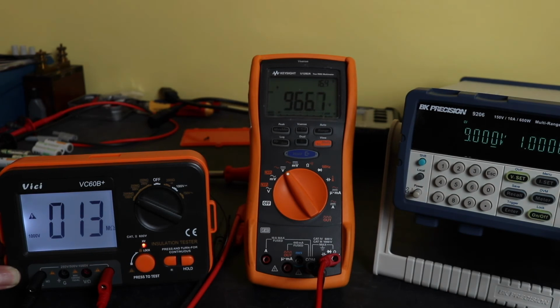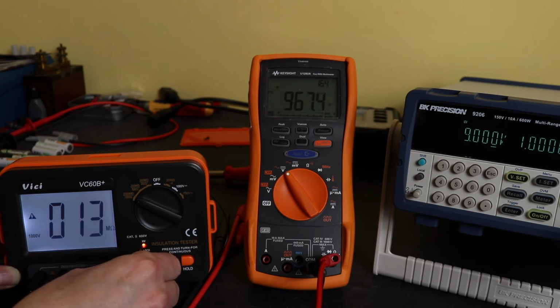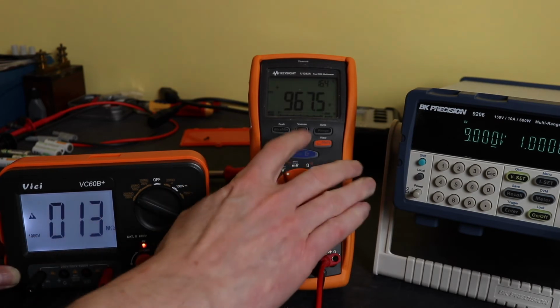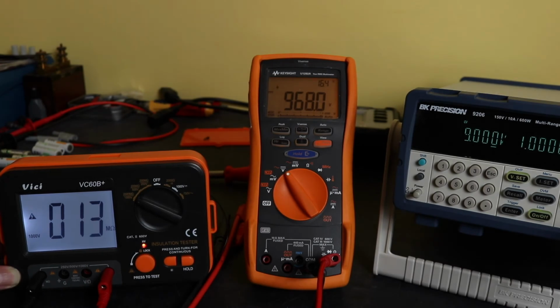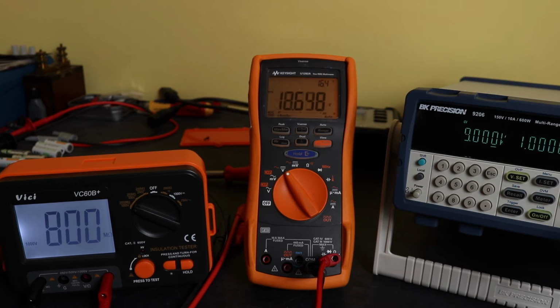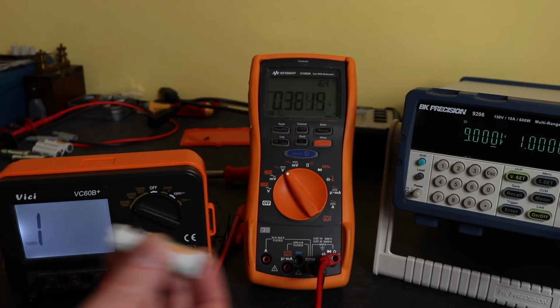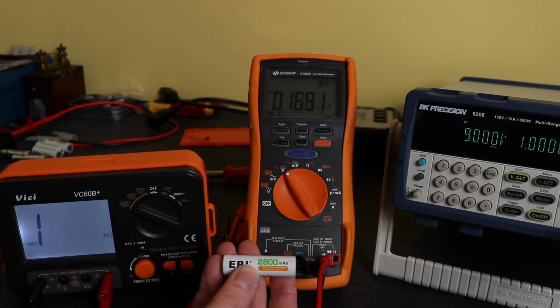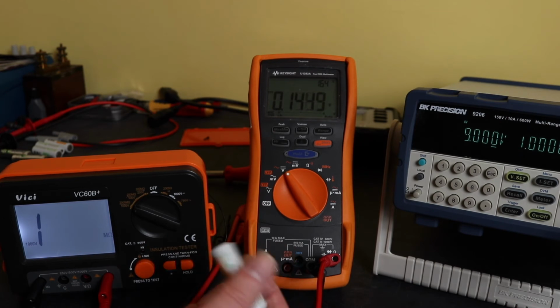Now with this 1000 volt, I can only get up to 966 volts, although it is creeping up, 967. That should be, to the IEC standard, it needs to be above 1000 volts. It can never be below the nominal voltage level of the insulation test. And that's further compounded by the choice in batteries. So I do use these rechargeable cells an awful lot.